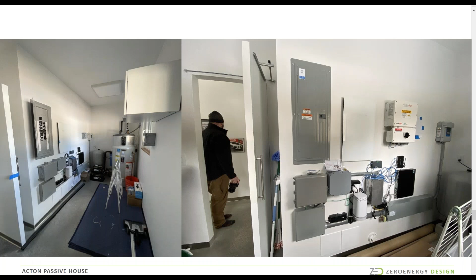Domestic hot water is a little hard to see. In the picture on the left, you'll see a tank in the background - that's a heat pump water heater. This is an electric domestic hot water system, pretty much off the shelf these days; all the major manufacturers make them. They extract heat from the air in the mechanical room and deliver that into the domestic hot water. They do have a cooling effect on the indoor air in the room where they're installed, and there's a compressor built in, so they make a little bit of noise. Expectations need to be properly set.